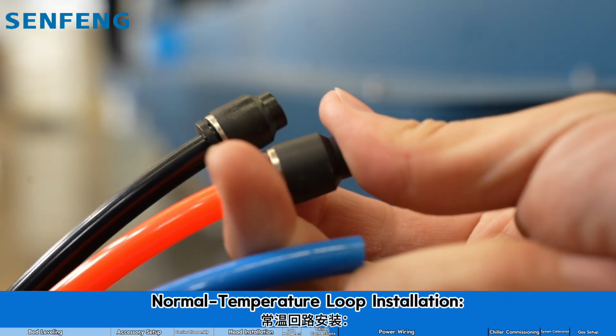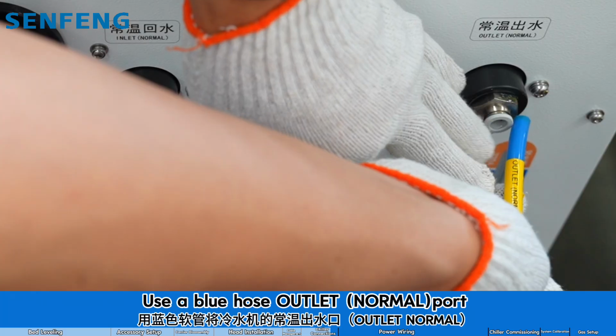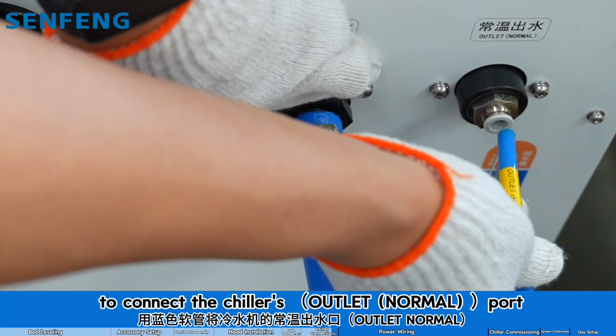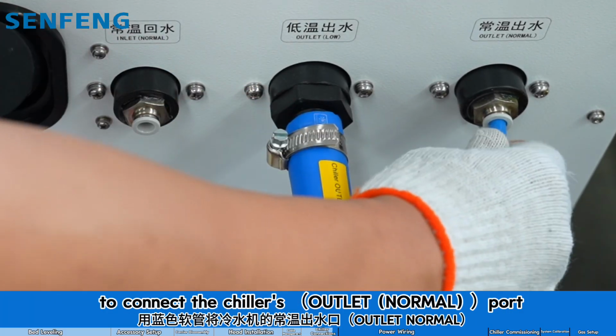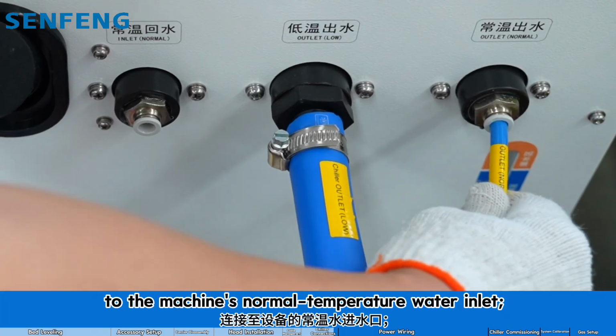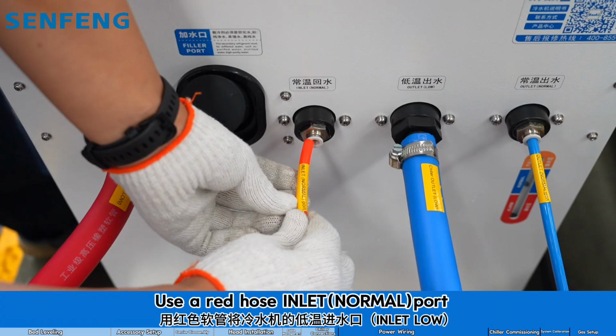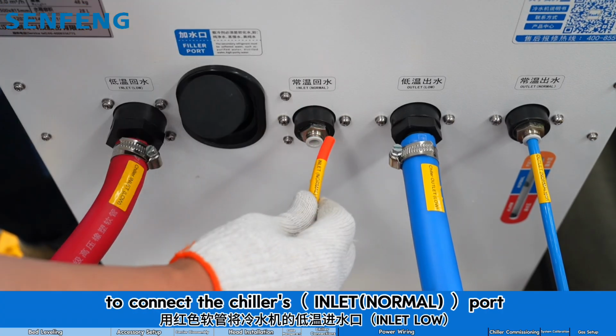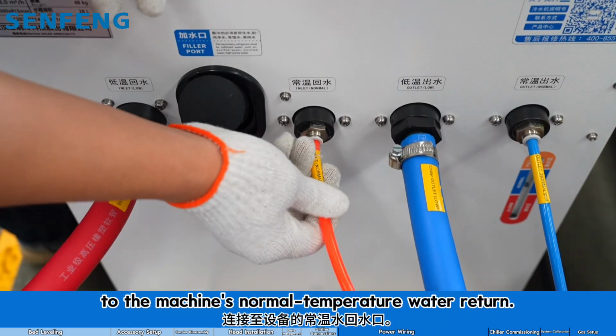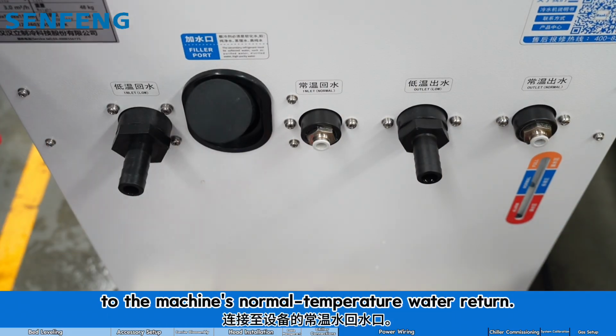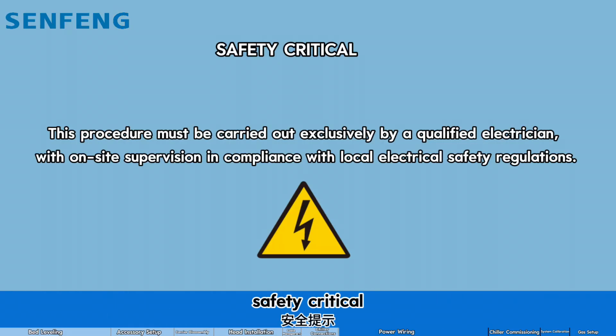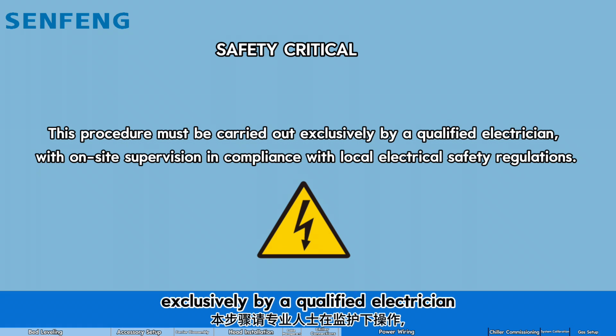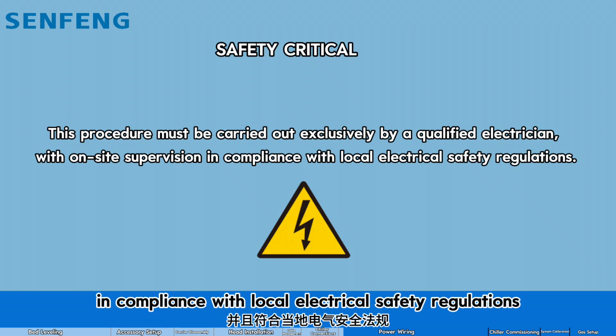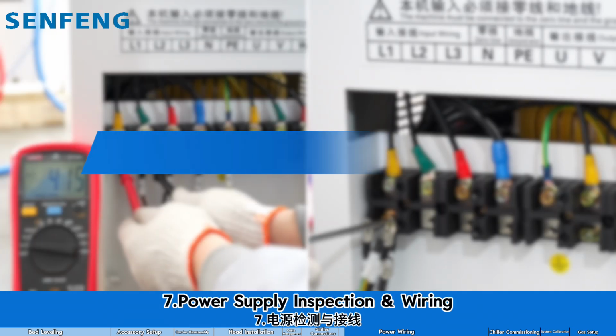Normal temperature loop installation. Use a blue hose, outlet, normal port, to connect the chiller's outlet, normal port, to the machine's normal temperature water inlet. Use a red hose, inlet normal port, to connect the chiller's inlet normal port to the machine's normal temperature water return. Safety critical. This procedure must be carried out exclusively by a qualified electrician with on-site supervision in compliance with local electrical safety regulations.